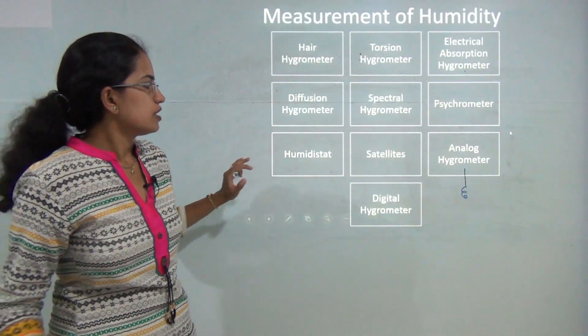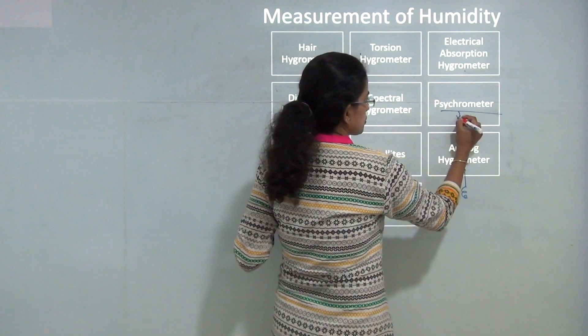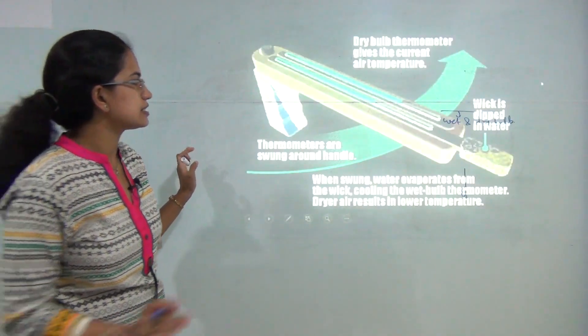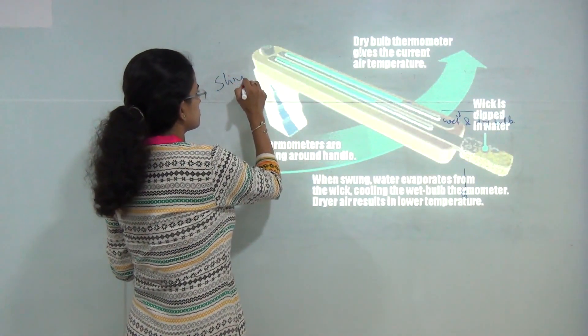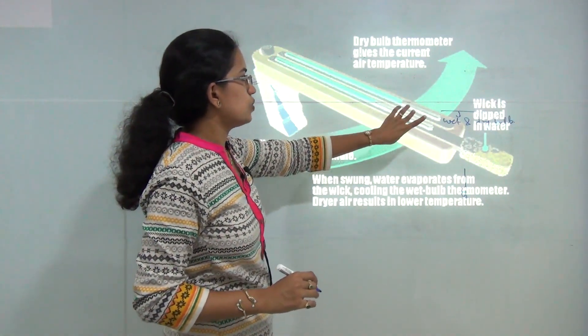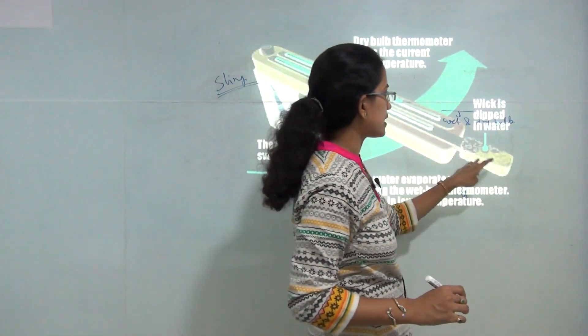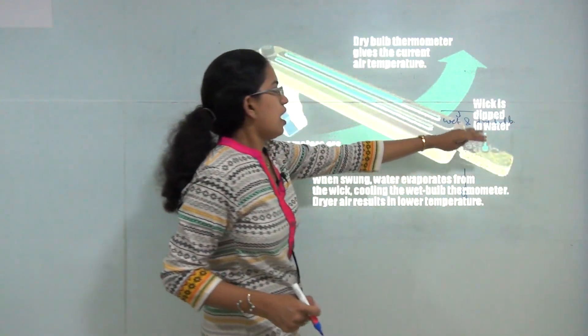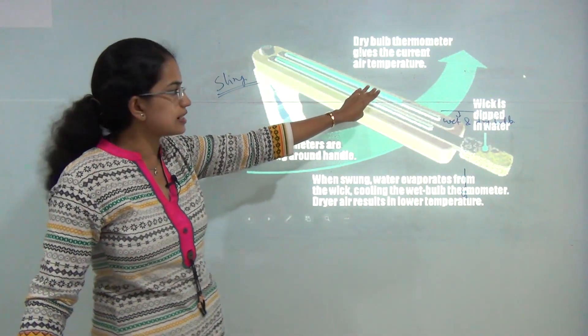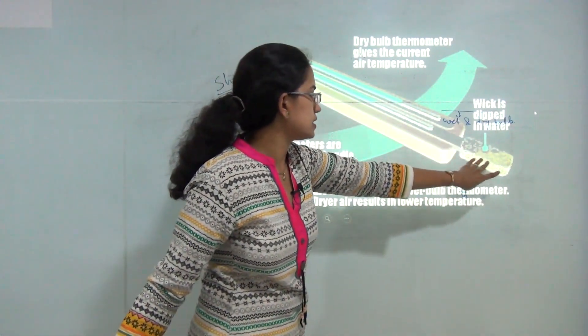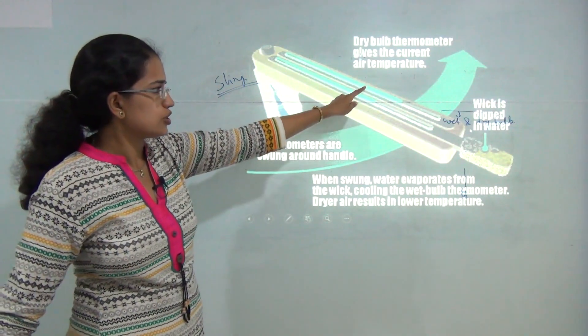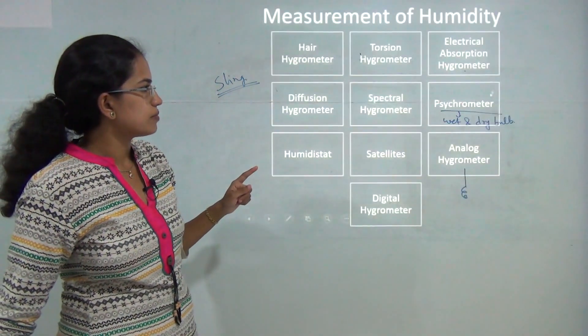This is a psychrometer, also known as a wet and dry bulb hygrometer. It is a sling arrangement, also known as a sling hygrometer. You have two measurements: one end is dipped in water and soaked with a cloth — that is the wet end — and the other end is dry. When water from the wet end evaporates, it leads to cooling and a lowering of temperature, which is how the wet and dry bulb hygrometer works.